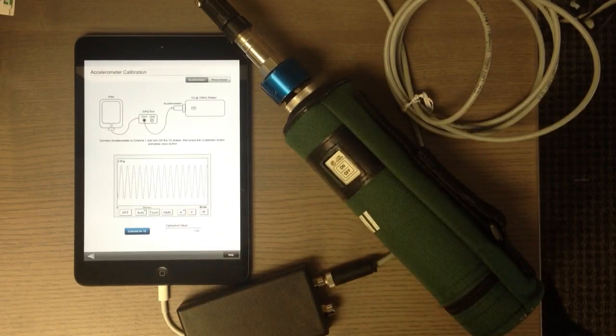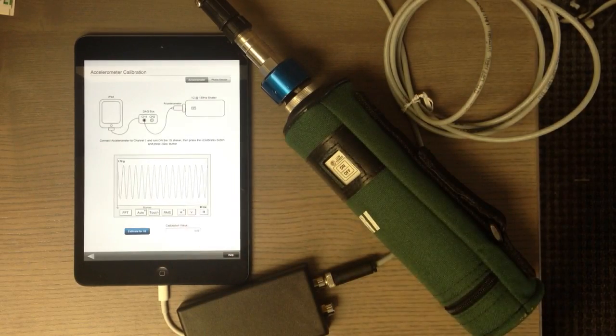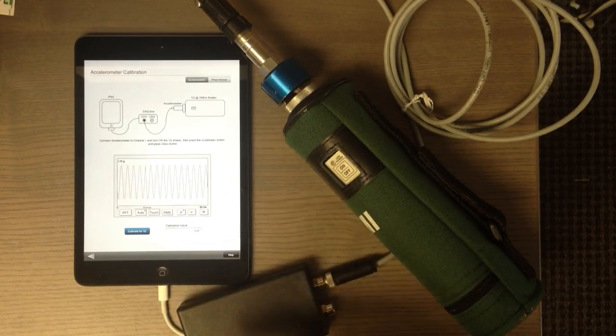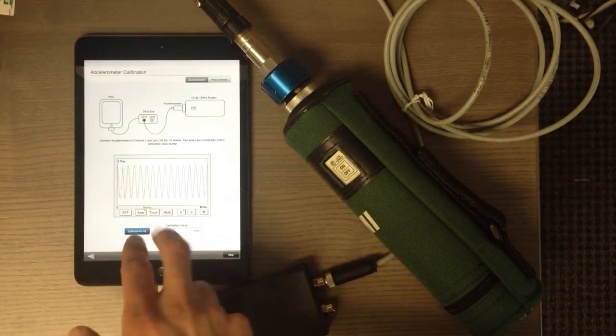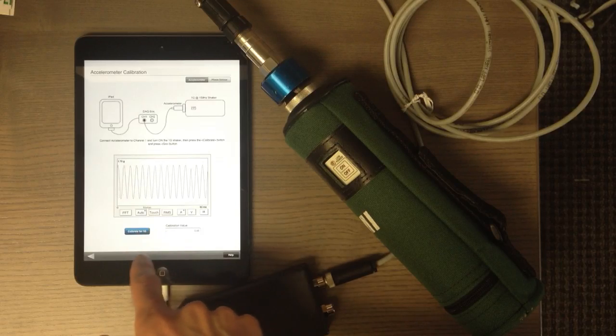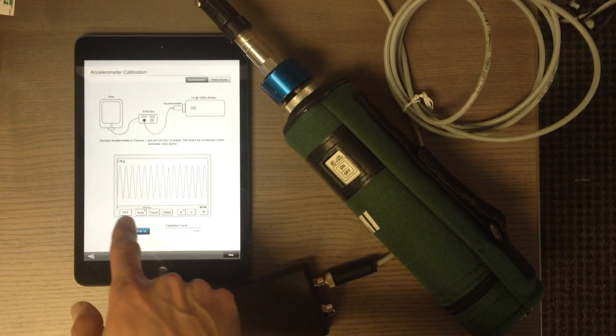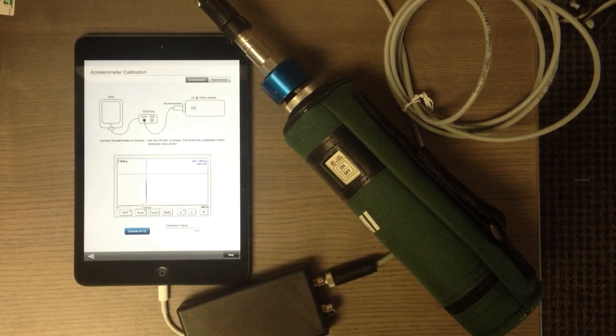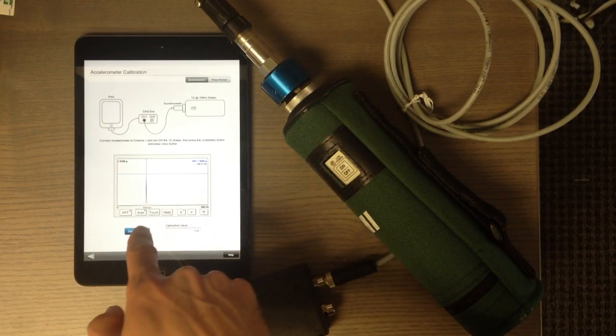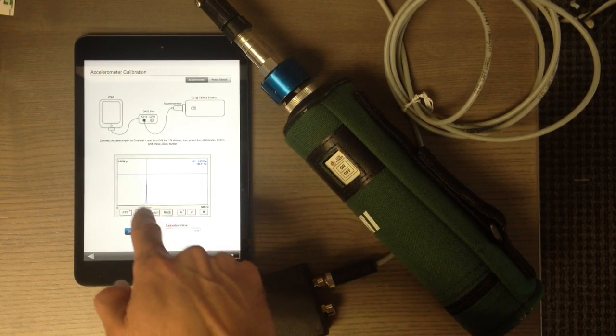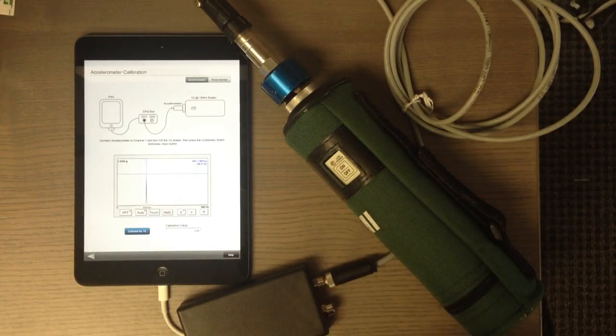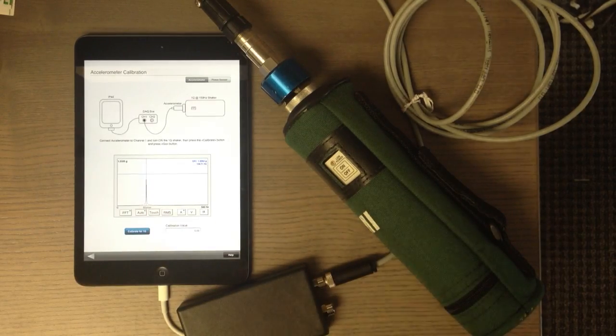The acceleration signal is here, but in order to calibrate, make sure you are in FFT. So when you're in FFT, you can see the signal which is around 158 Hertz and you see the amplitude of the signal.